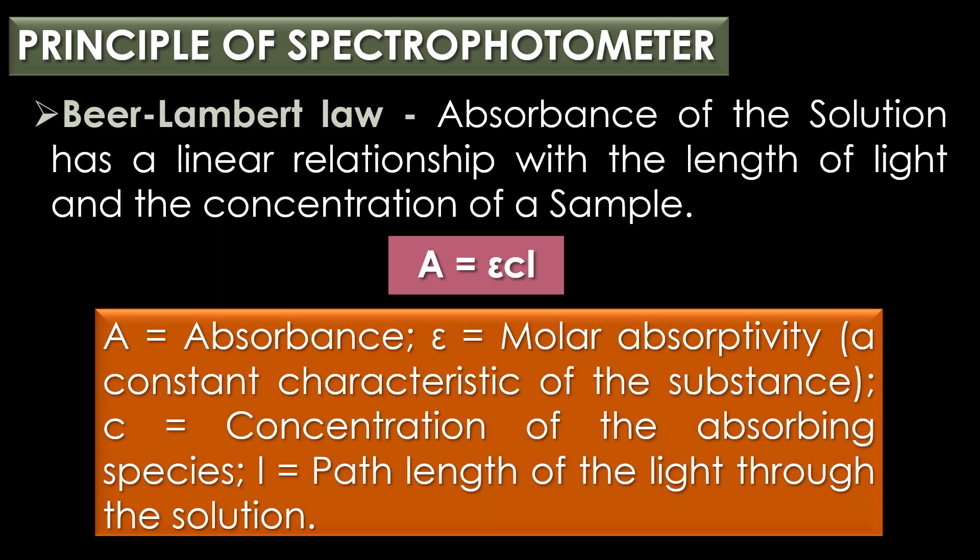A spectrophotometer is based on the Beer-Lambert's Law, which states that the absorbance of a solution has a linear relationship with the length of light path and the concentration of a sample. Mathematically it can be represented as A = εcl, where A is absorbance, ε (epsilon) represents the molar absorptivity — a constant characteristic of a substance — c represents the concentration of the absorbing species, and l represents the path length of the light through the solution.